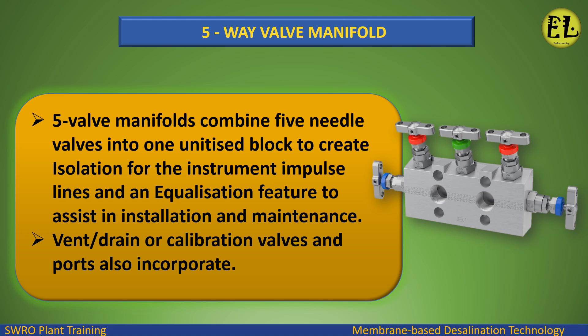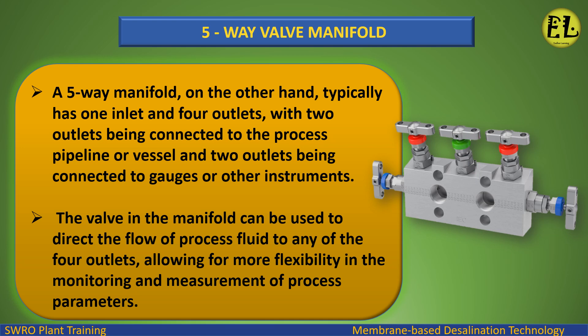Five-way valve manifold: five-valve manifolds combine five needle valves into one manifold block to create isolation for the instrument impulse lines and an equalization feature to assist in installation and maintenance. Vent, drain, or calibration valves and ports are also incorporated. A five-way manifold typically has one inlet and four outlets, with two outlets connected to the process pipeline or vessel and two outlets connected to gauges or other instruments. The valves in the manifold can be used to direct the flow of process fluid to any of the four outlets, allowing for more flexibility in monitoring and measurement of process parameters.